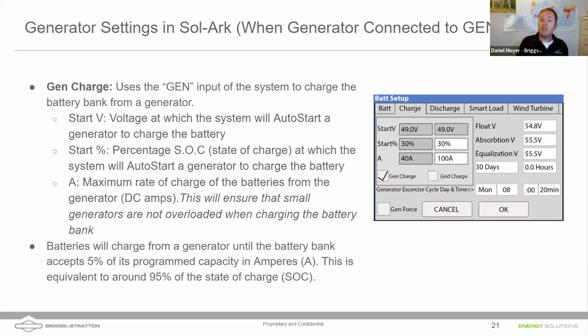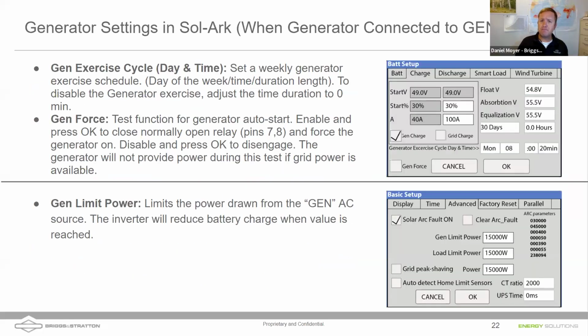Once that generator does start, it's going to charge up those batteries almost completely full. We're not going to float the batteries on a generator, but we're going to get them full. We're going to get them up to about 95% state of charge, and then we're going to shut that generator off. I will say that if you're using a generator on a grid port, there are ways to dynamically adjust when and how much of a charge we put on the batteries out of a generator. Check out, again, some of John's talks on Sol-Ark University to get into more of those details.